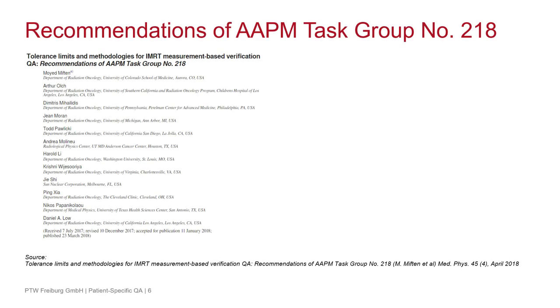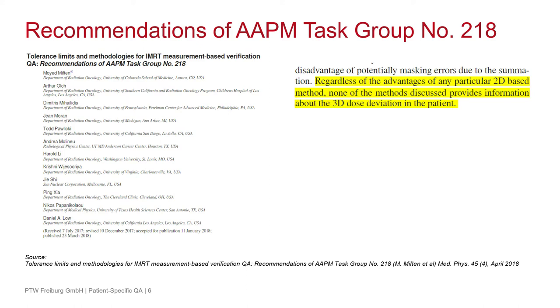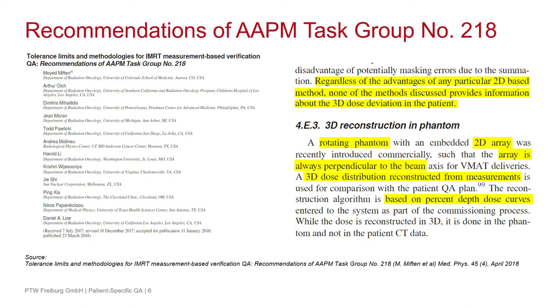3D measurements are also already mentioned in the AAPM TG-218 report. They present the possibilities for two-dimensional patient-specific QA and state that regardless of the advantages of any particular two-dimensional-based method, none of the methods discussed provides information about the 3D dose deviation in the patient. Additionally, they describe a system similar to our Octavius 4D: a rotating phantom with a two-dimensional array always perpendicular to the beam, yielding a 3D dose distribution reconstructed only from measurements based on percent depth-dose curves.